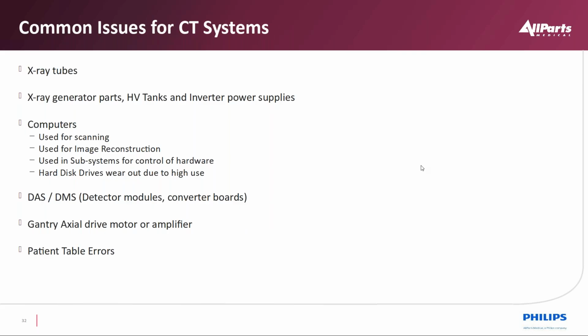So, common issues with CT scanners. This is our cost to serve when we're starting to look here. X-ray tubes are one of the highest failure items. Not that they fail regularly, but from a cost perspective, it's one of our highest issues. We're talking about X-ray tubes anywhere from the mid 50,000s all the way to 240,000, based on the scanner.